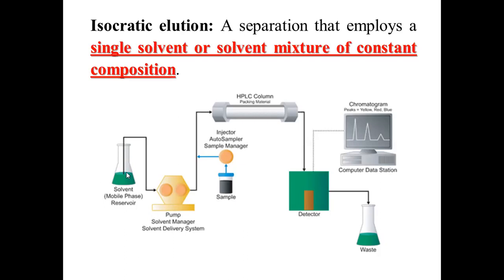So only one solvent reservoir is enough, because if you are using two different solvents, you will mix them in some proportion. You will take them in the solvent reservoir and fix that to the pump, and its journey will be fixed towards the chromatographic column. So you will get the chromatogram at the end, and these chromatograms are obtained by the elution of the solutes using the same mobile phase. If there were 10 solutes, all those 10 solutes are eluted by using the same mobile phase. This is called isocratic elution.